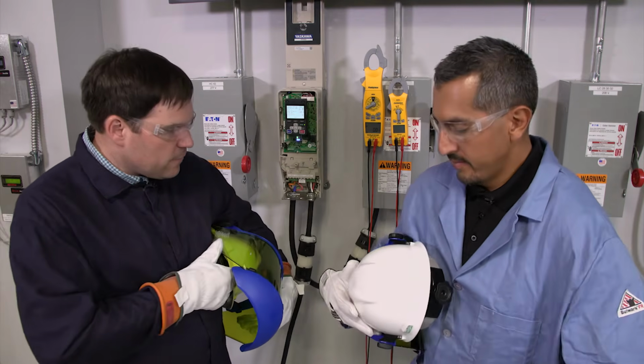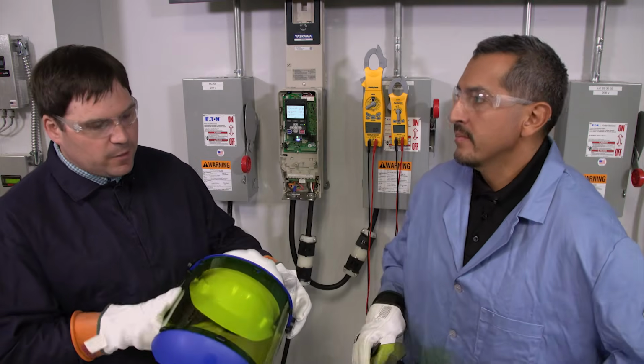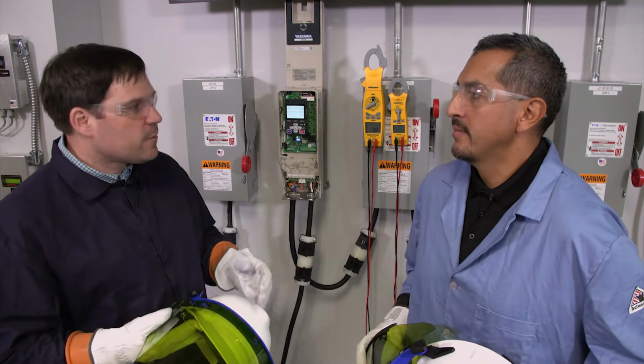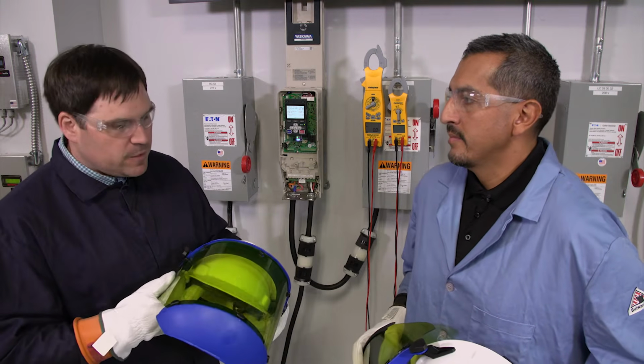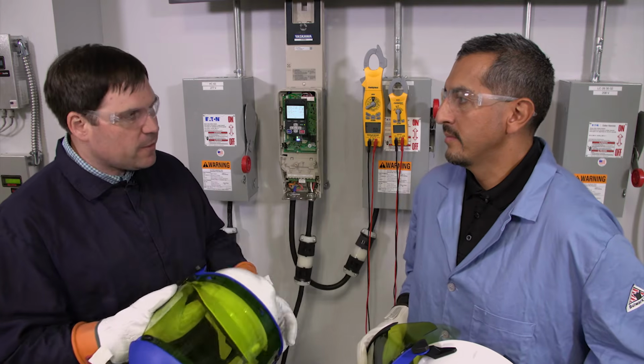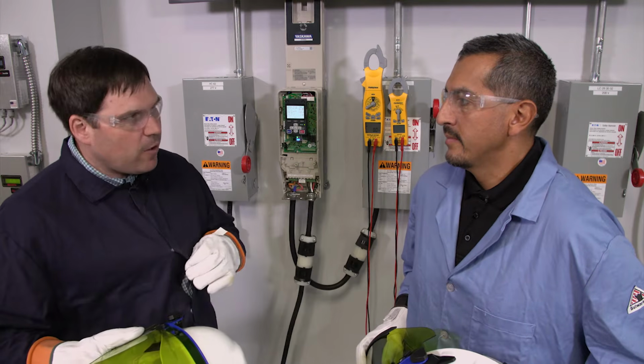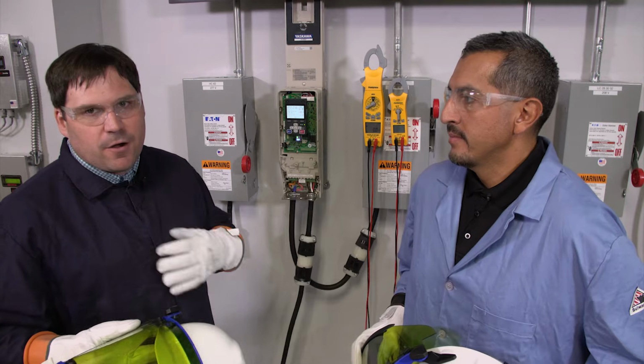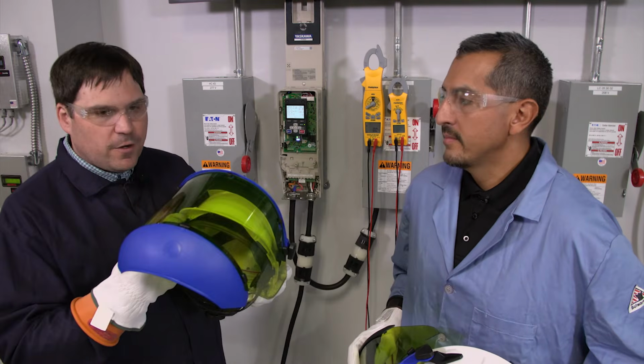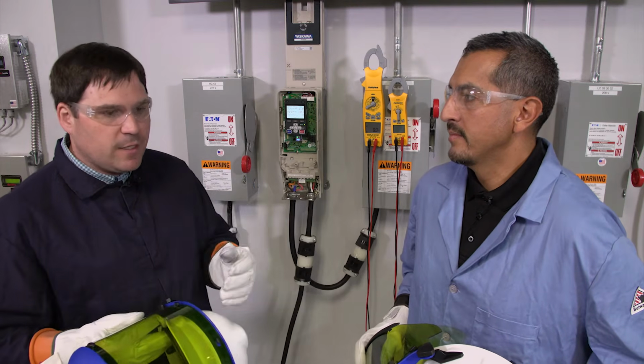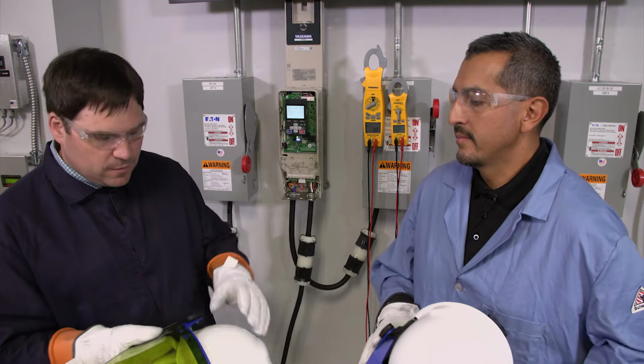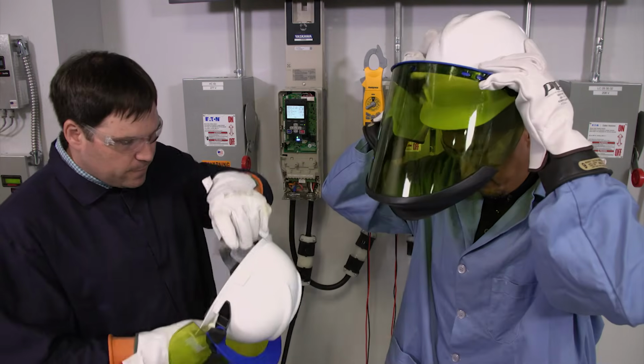Yeah, Tony. The first thing we need to talk about is safety when taking electrical measurements. These are 3-phase power systems, so there are other hazards to be concerned with, notably arc flash. You can see Tony and I have on our arc-rated clothing. We're going to put on our shields over our safety glasses, and we have our voltage-rated gloves. So let's get after it.